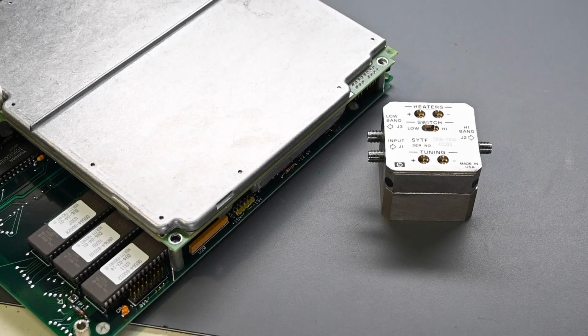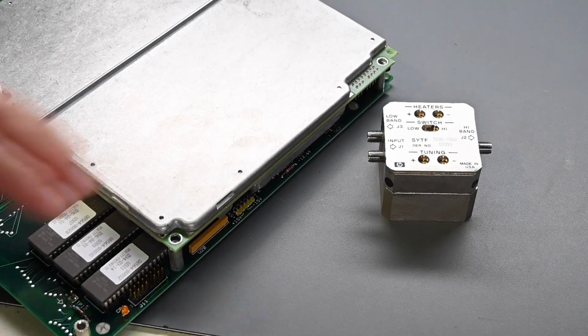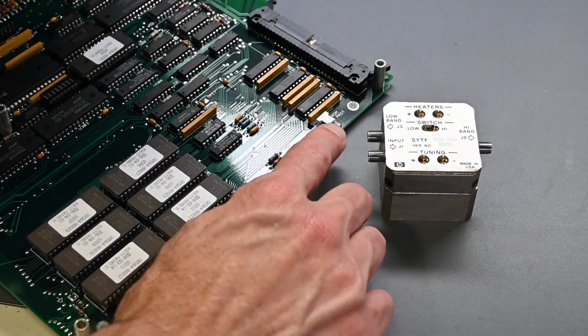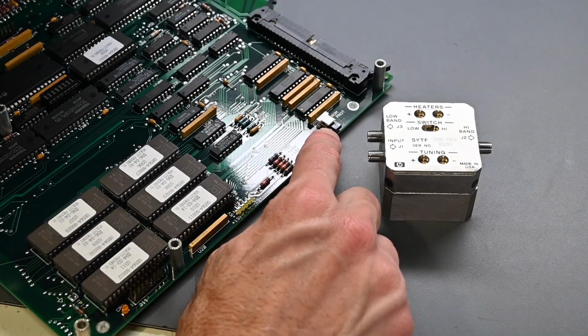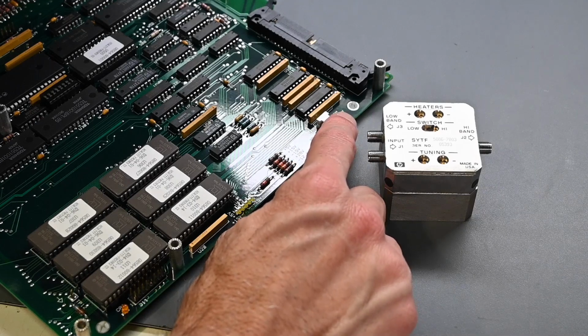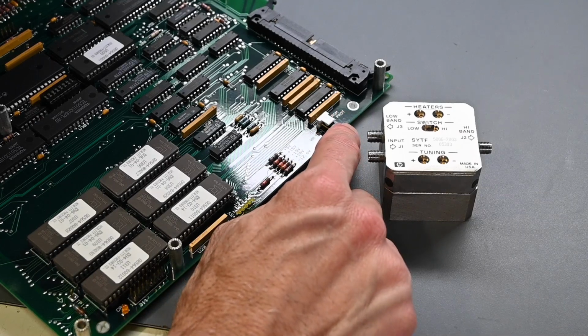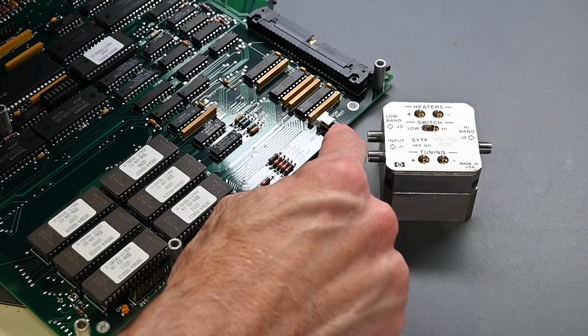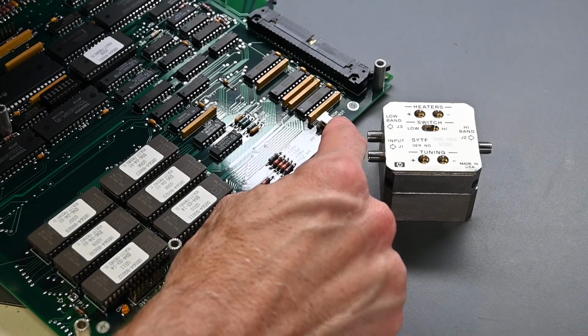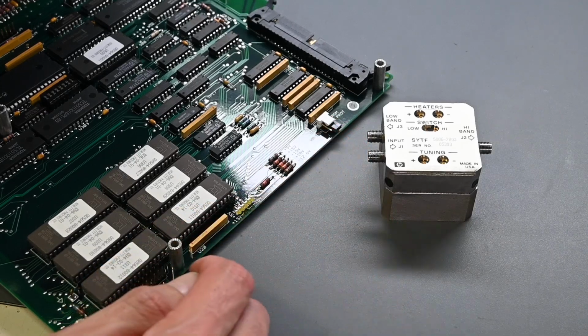Now the final step that I'll need to do is to calibrate the replacement module, and I'll take you through that process. One of the steps in the calibration procedures is to move this jumper right here. So this is an EEPROM protection. There's a write protect and a write enable. Of course it's in the protection position right now. This little black colored portion is unplugged and just moved over to the other position.